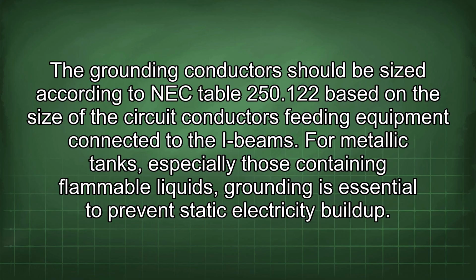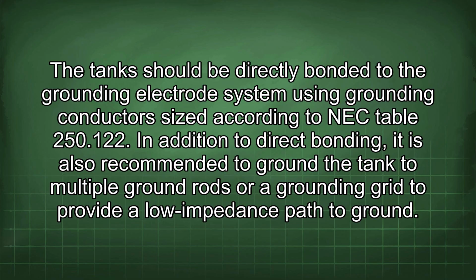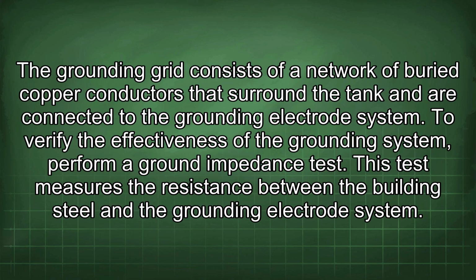For metallic tanks, especially those containing flammable liquids, grounding is essential to prevent static electricity buildup. The tank should be directly bonded to the grounding electrode system using grounding conductors sized according to NEC Table 250.122. In addition to direct bonding, it is also recommended to ground the tank to multiple ground rods or a grounding grid to provide a low impedance path to ground. The grounding grid consists of a network of buried copper conductors that surround the tank and are connected to the grounding electrode system. To verify the effectiveness of the grounding system, perform a ground impedance test. This test measures the resistance between the building steel and the grounding electrode system.